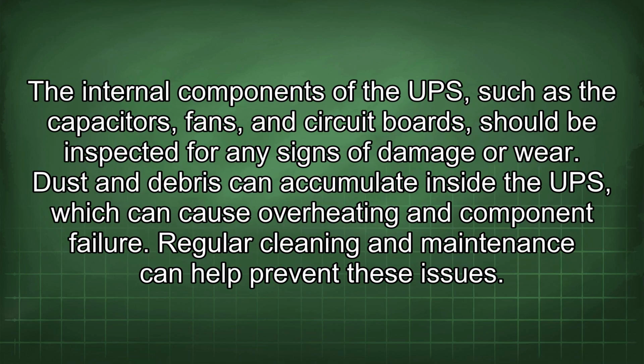The internal components of the UPS, such as the capacitors, fans, and circuit boards, should be inspected for any signs of damage or wear. Dust and debris can accumulate inside the UPS, which can cause overheating and component failure. Regular cleaning and maintenance can help prevent these issues.